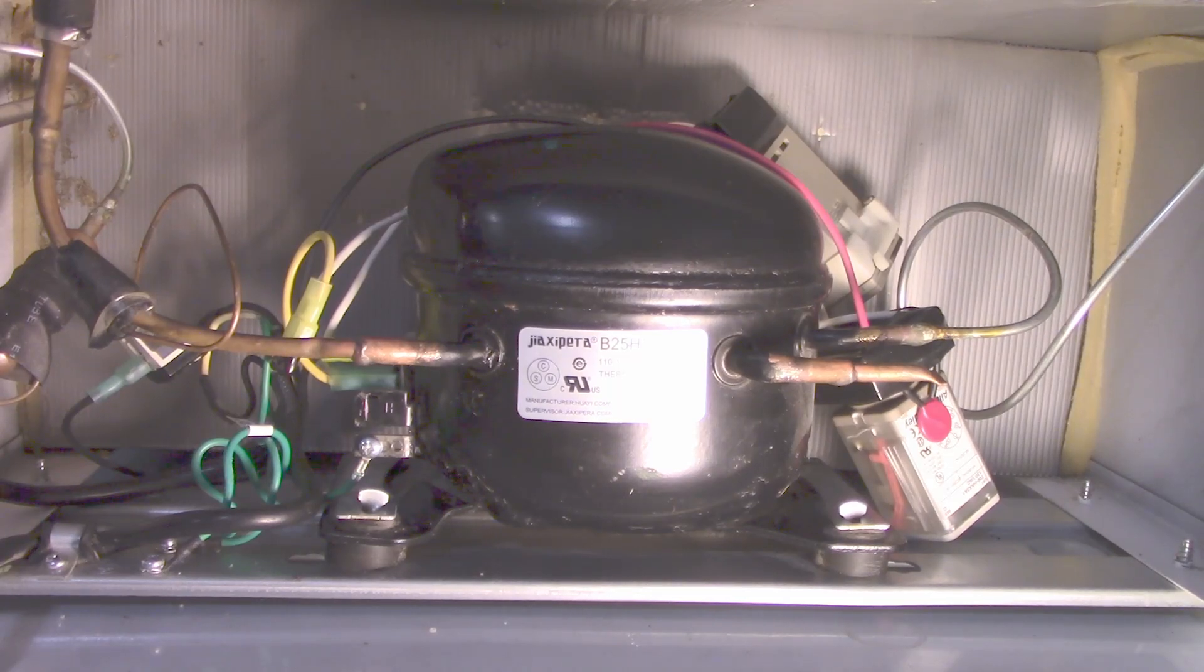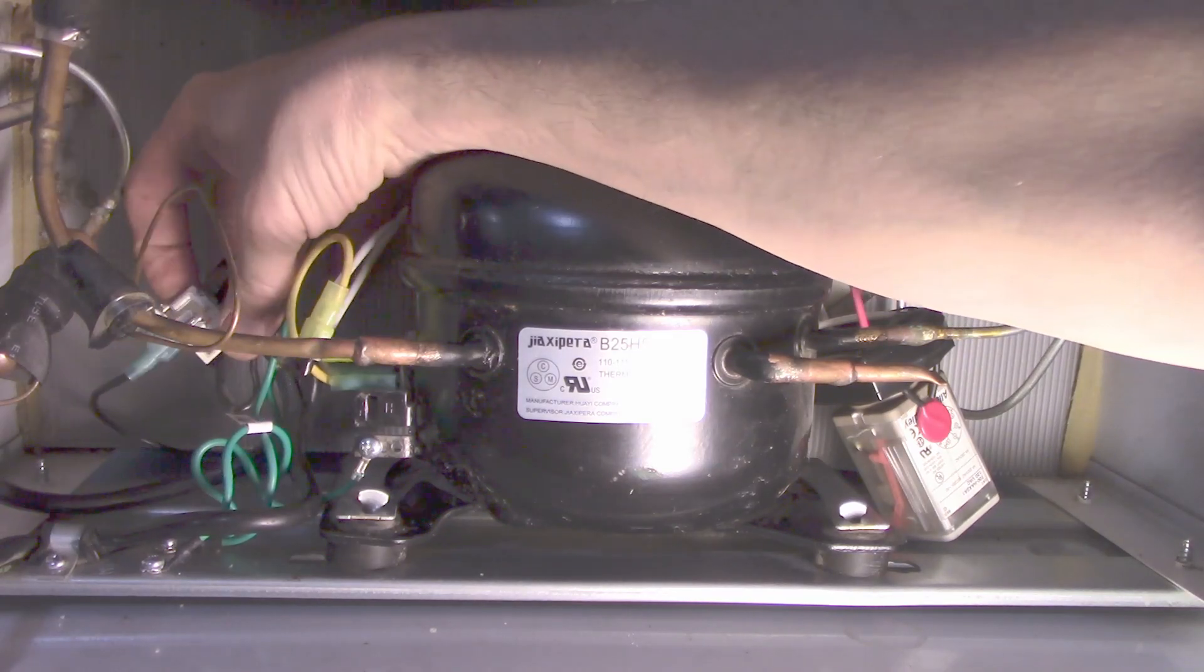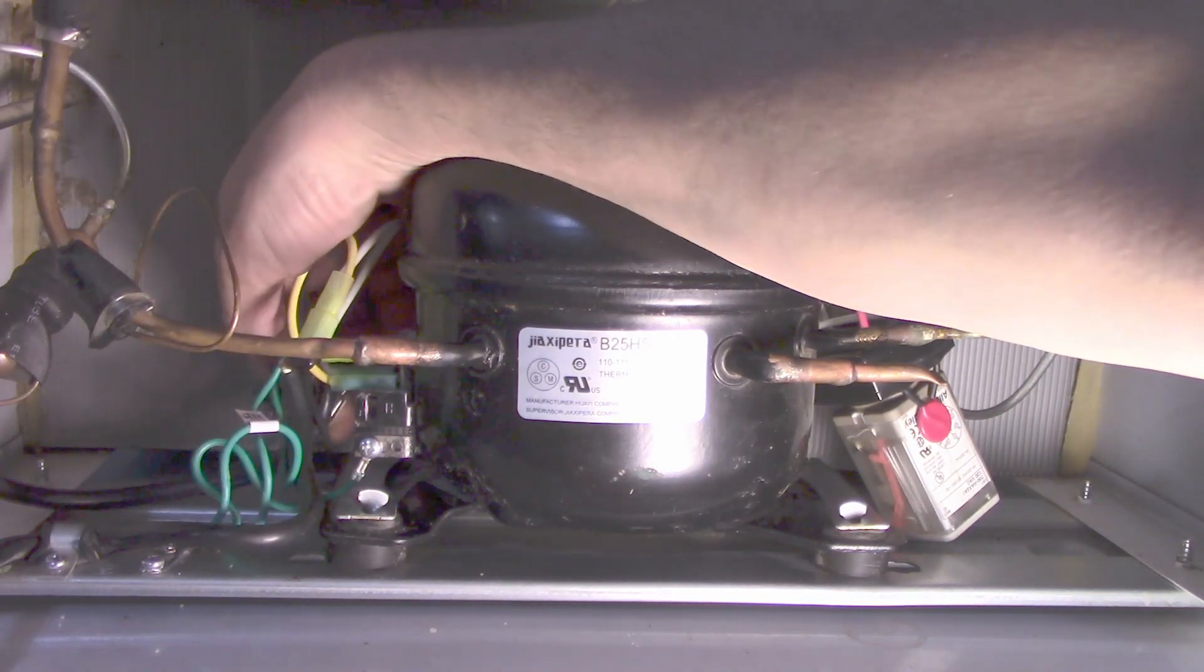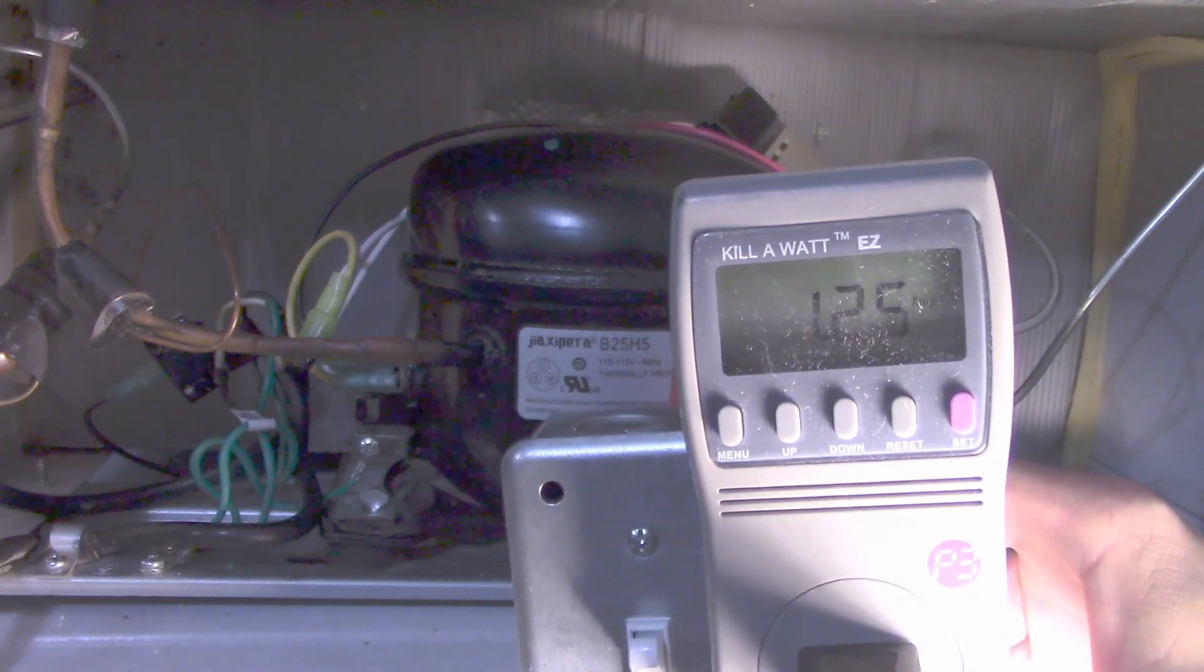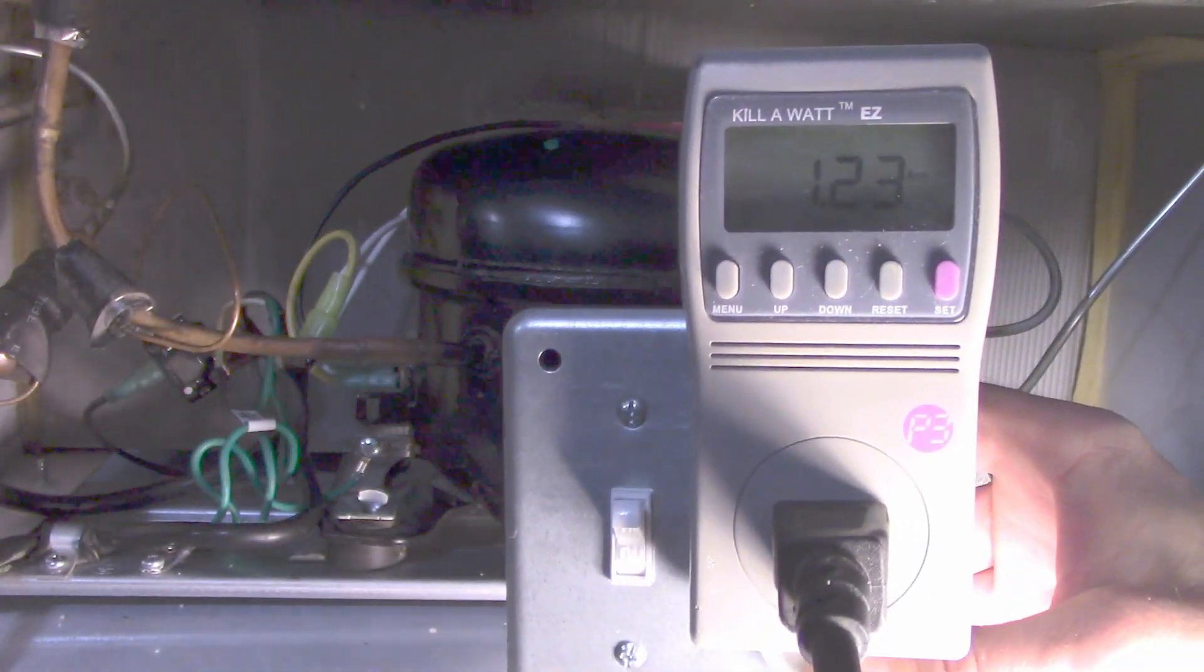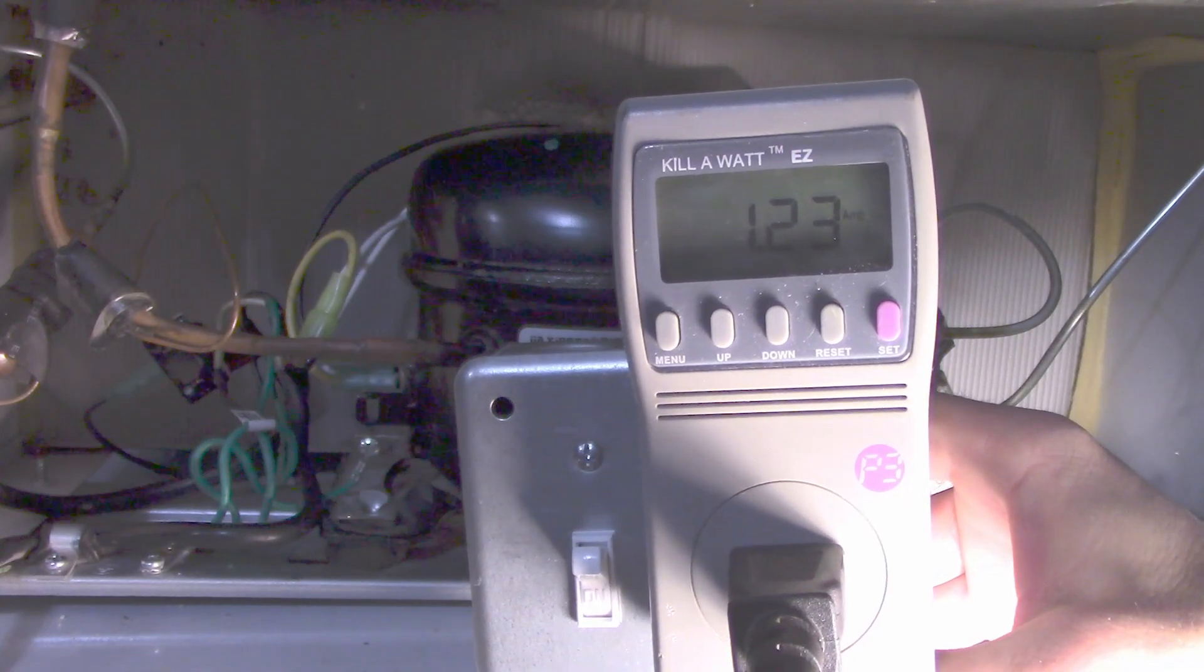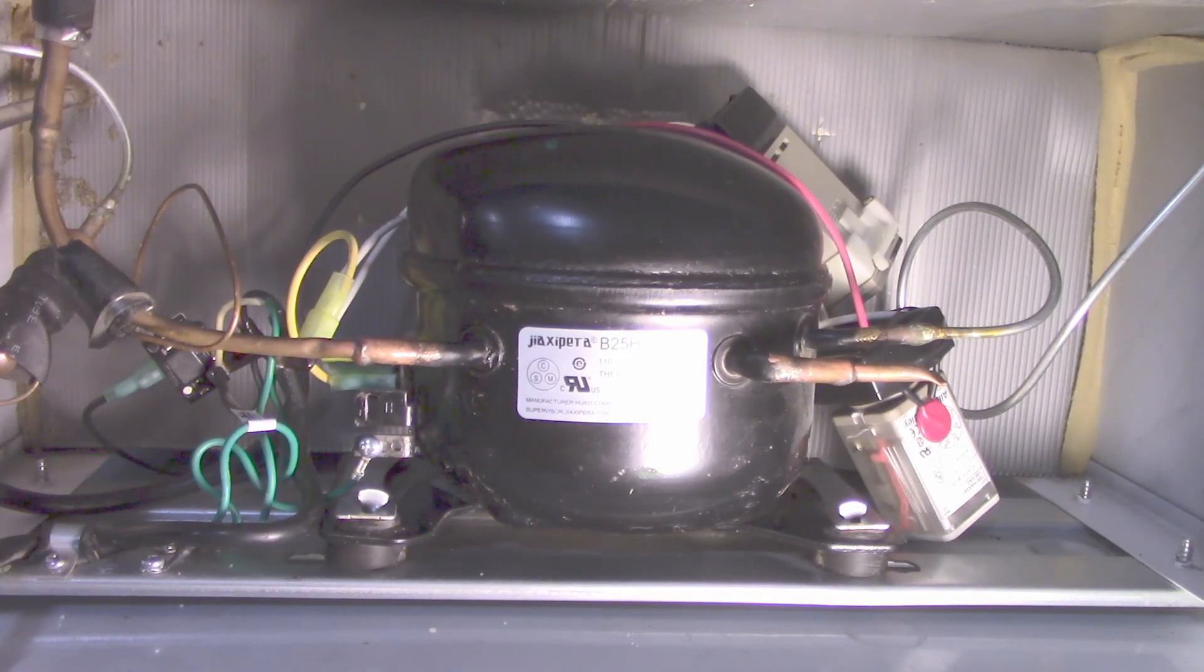All right, so I've got everything kind of cobbled up in here, nothing's touching anything. The only live part I have exposed is right here, the thermal overload, and I'll probably wrap that with tape just to be safe. So here we go. And it's running. Here's the amp reading, if you can see that, 1.25 amps. It's running good. Let's wipe that off so you can see it. Now it's down to 1.23 amps.